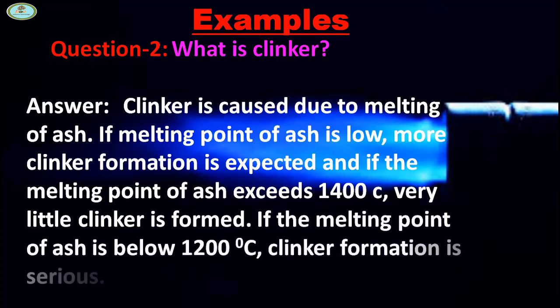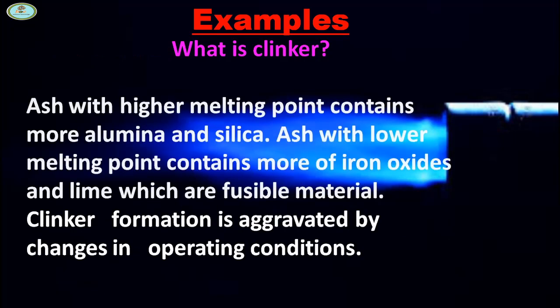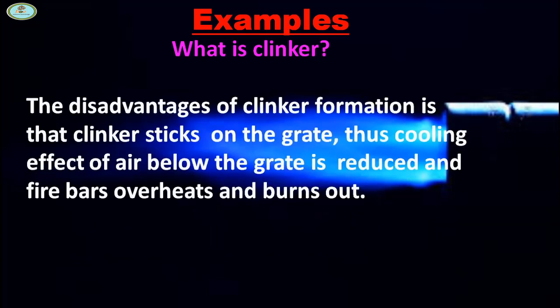If the melting point of ash is below 1200 degrees Celsius, clinker formation is serious. Ash with higher melting point contains more alumina and silica. Ash with lower melting point contains more iron oxides and lime, which are fusible materials. Clinker formation is aggravated by changes in operating conditions.